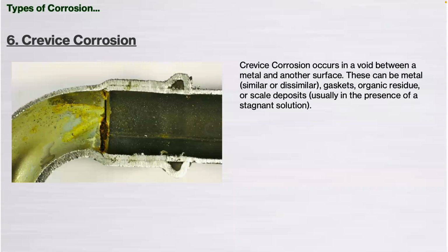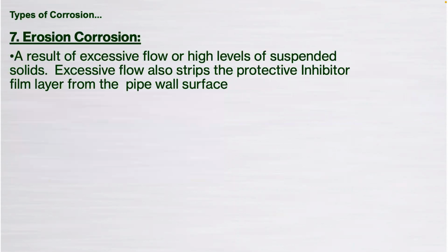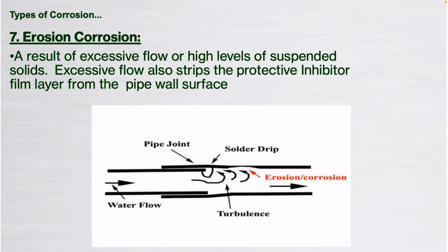When that pipe has been pushed into the joint, there's a huge crevice that's been left there, and that leaves a pocket of stagnant water. And again, similar to the other corrosions we've discussed, whereby you've got different levels of oxygen, and obviously no treatment can get access to there either. So you have this crevice corrosion occurring. Can look actually sometimes worse than that. Sometimes you can have flanges that will fail, where flange joints haven't been put together equally. Erosion corrosion, so too much flow or high levels of suspended solids.